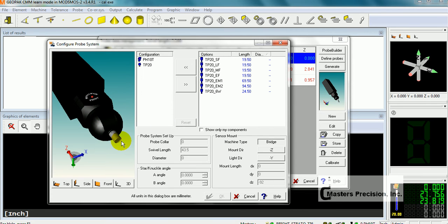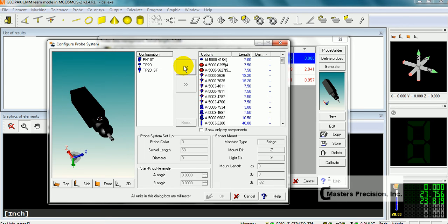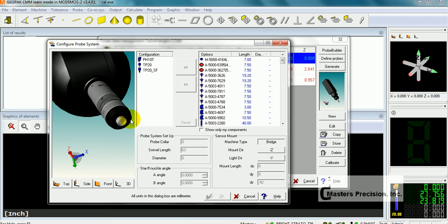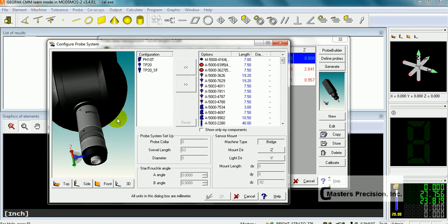Now I'm going to tell it what module I have. I have a standard force, which is the black ring. I'm going to send it over. Bring it back in again so we can see it. As you can see, it has a black collar. There are different colored collars. There's a gray one, which is a medium force, which takes a little bit heavier stylus than the standard force. The biggest one they have as far as weight goes is the extended force. This takes the most. And a light blue ring is the low force module. It needs to be used with lighter styluses. It has a lower trigger force. The Renishaw catalog describes what stylus configurations can go with what module, so I suggest you check it out.